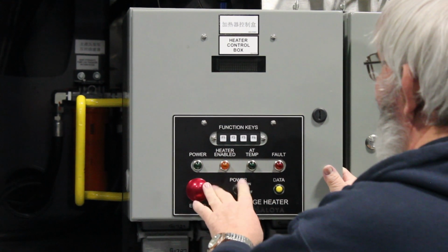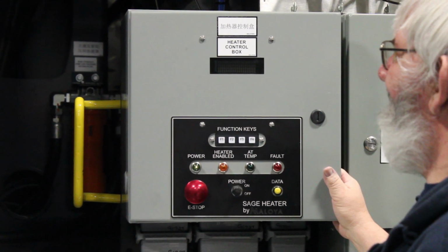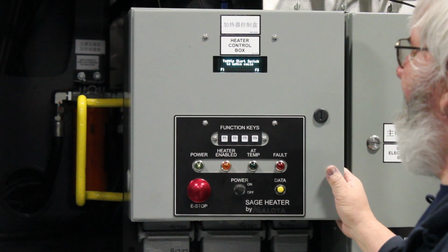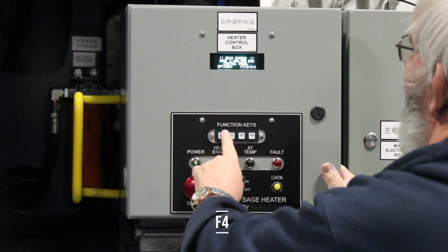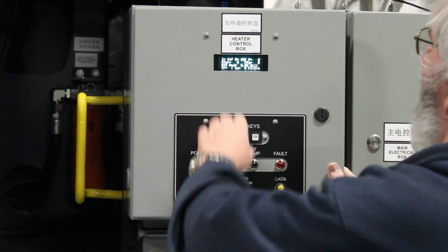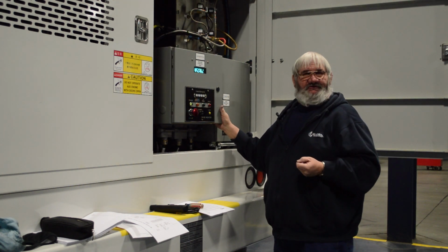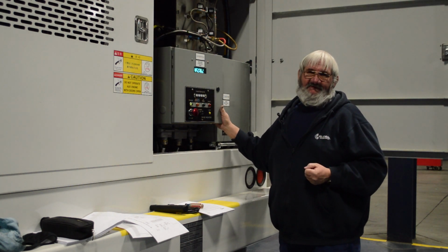escape out of this here. We'll cheat again, got the power off, repowered it up. When you're doing a heater burn, we look at your fuel pressure set point and your fuel pressure actual. While you're doing that heater burn, those two numbers should maintain or stay very close to each other.